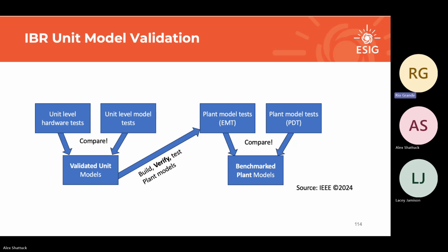Because if you do this design evaluation right, it's the same logic steps as doing the grid model validation and switching parameters for your real site. So even if you do a design evaluation for your plant model without weak grid tuning, you can be pretty sure that if I tweak some parameters for weak grid, I'll probably still have a good match model. Again, outside of bugs and hot fixes and stuff like that.